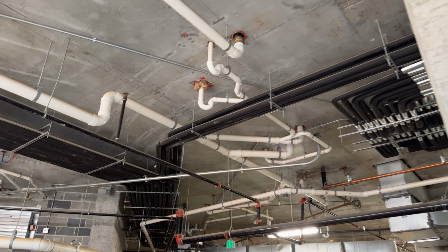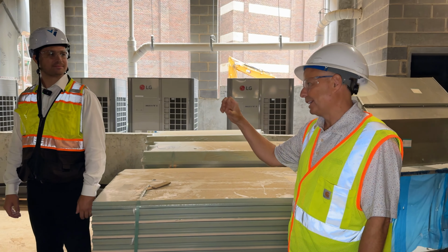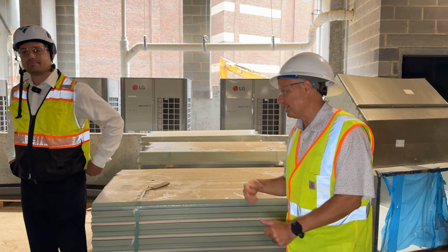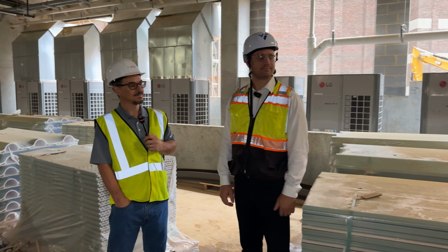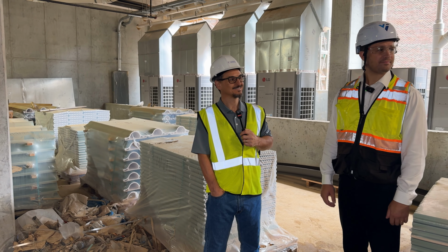Exactly. And we'll see crimped insulation too, and then you'll get condensation where they crimped the insulation, so you don't have that actual half-inch insulation when you crimp it, and all of a sudden you've got potential for metal to metal contact, and you get that condensation leak.